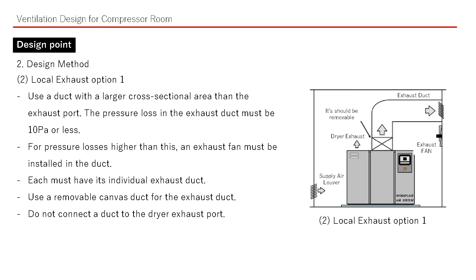About local exhaust Option 1, using a fan for the room. 1. Use a duct with a larger cross-sectional area than the exhaust port. 2. The pressure loss in the exhaust duct must be 10 pascals or less. For pressure losses higher than this, an exhaust fan must be installed in the duct. 3. Each unit must have its individual exhaust duct. 4. Use a removable canvas duct for the exhaust duct. 5. Do not connect a duct to the dryer exhaust port.